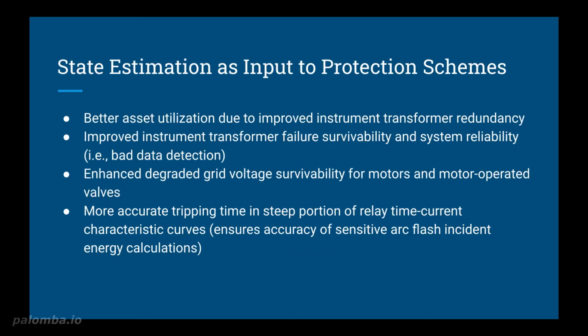So these protective devices must not trip prior to the degraded voltage relay timer timeout operation. Obviously, they can then successfully transfer onto the on-site emergency diesel generators. However, motors draw increased current levels when applied with low voltages, which significantly increases the risk of tripping thermal overload relays, which would obviously result in a common failure of equipment throughout the plant. So this is a huge problem in the eyes of the Nuclear Regulatory Commission.